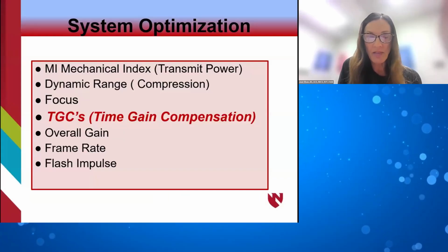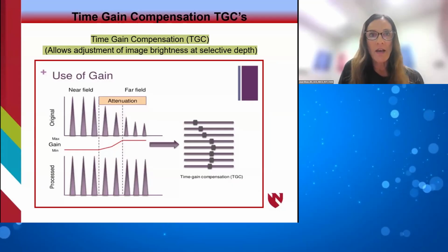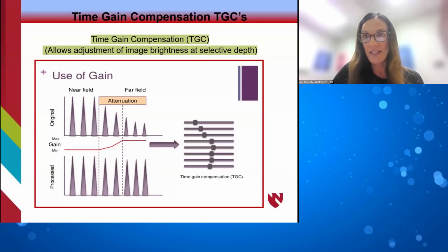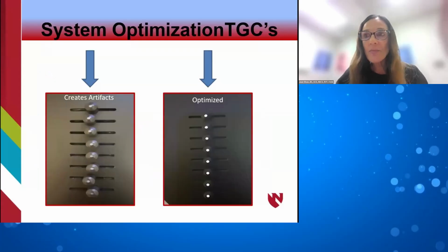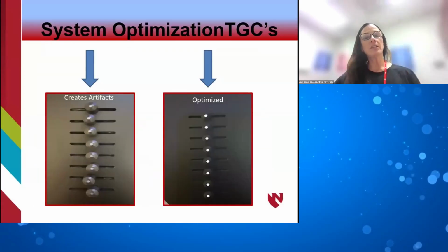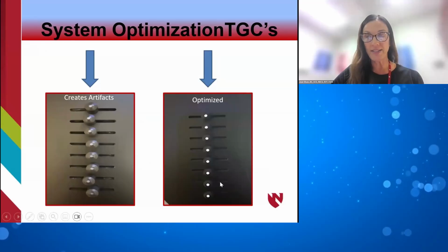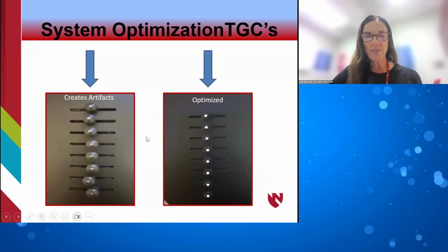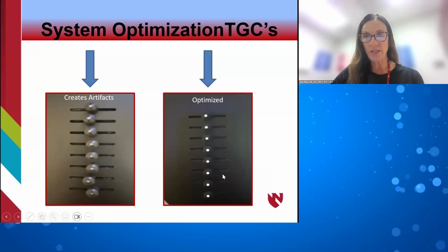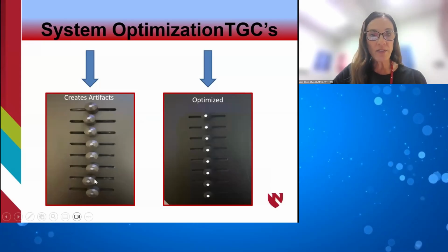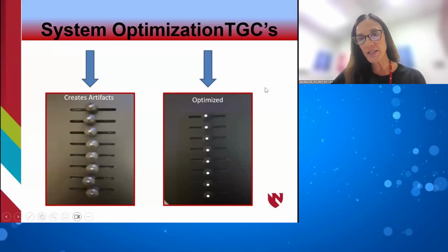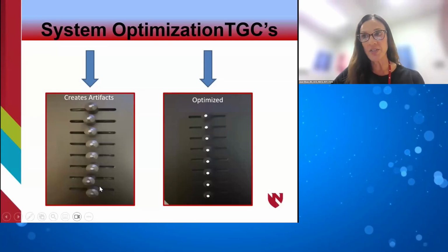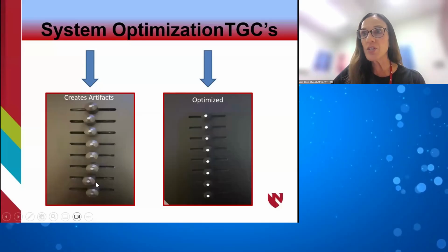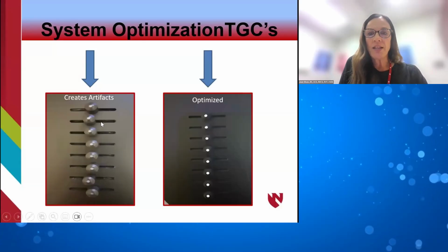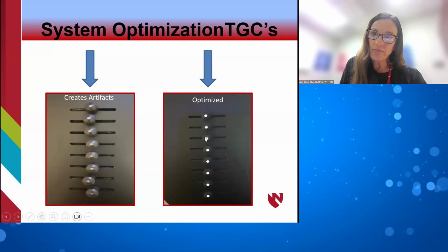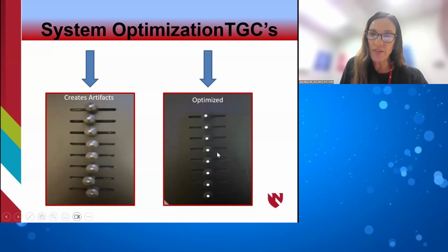Your TGCs, time gain compensation, allow for adjustment of image brightness at a selective depth. This is very important, especially when you're doing contrast imaging, to make sure that your TGCs are set at home. When we do our low MI imaging on our machine, home is in the middle. If you have one of these off just a little bit, it'll make a huge difference, and it can create artifacts and a lot of issues, especially if you're doing perfusion imaging. It can create perfusion defects that aren't there. So it is vitally important that you utilize your TGCs and make sure they're set up correctly.